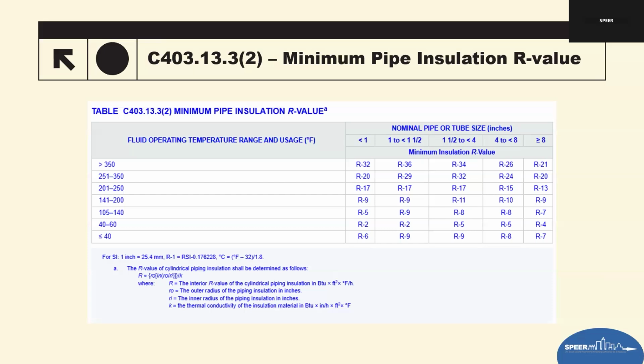So confirm that what it says on the equipment actually is what they're listing on the plans for the pipe. Confirm the R value shown in the schedules matches the table requirements. Check whether the designer used the tables, either inches or R value. And then review the insulation submittals for conductivity. So it's basically the K value. That usually comes from whatever manufacturer made the insulation product. You'll be able to find that in those product data.